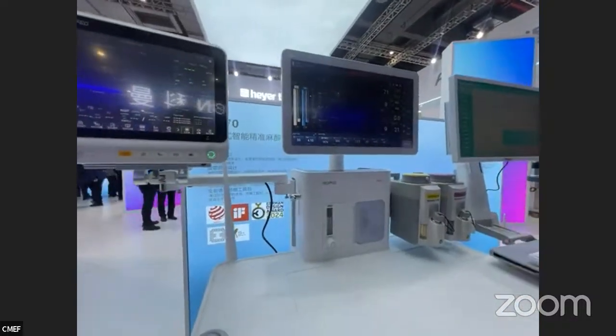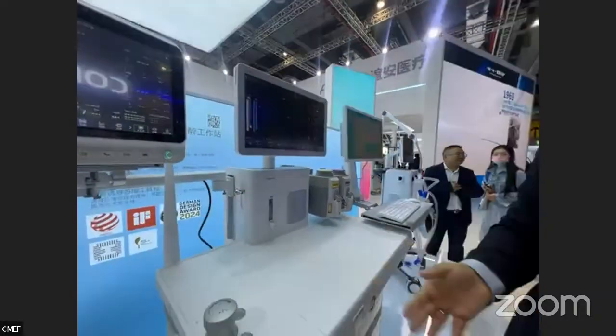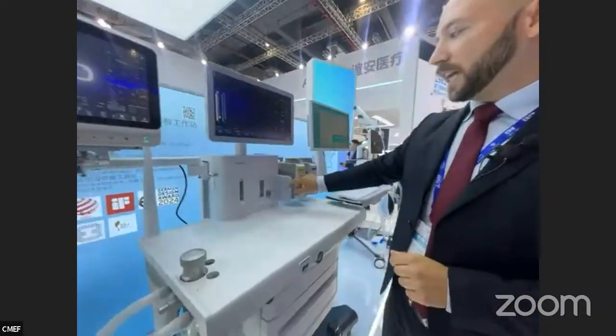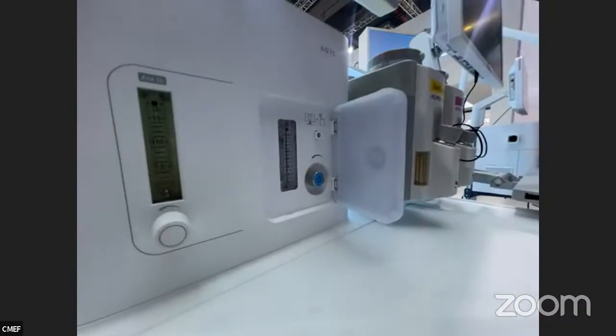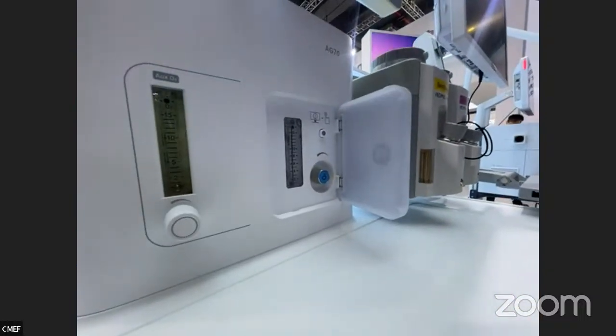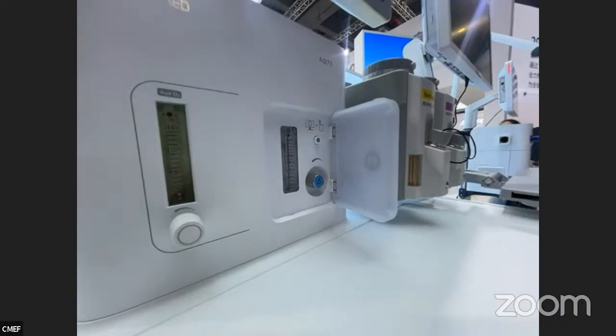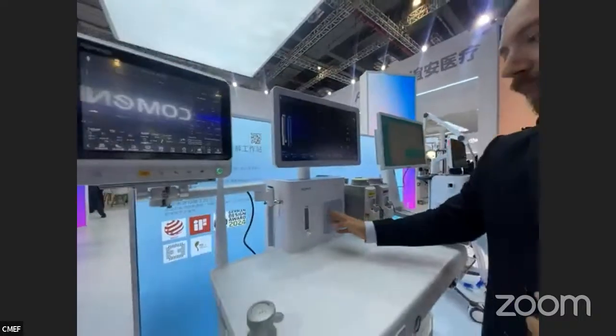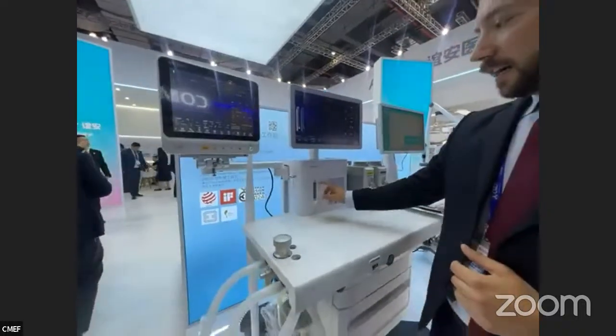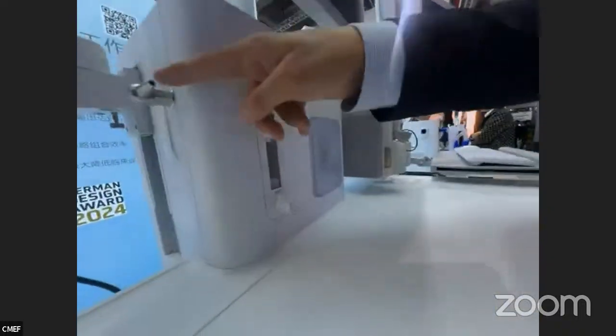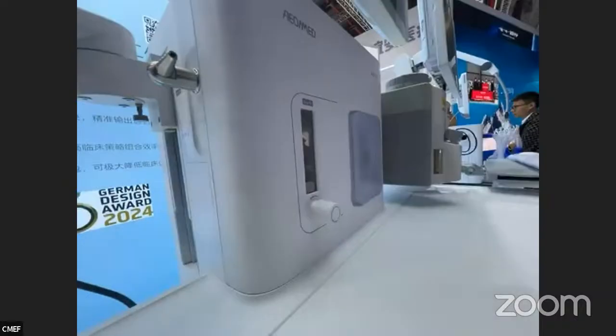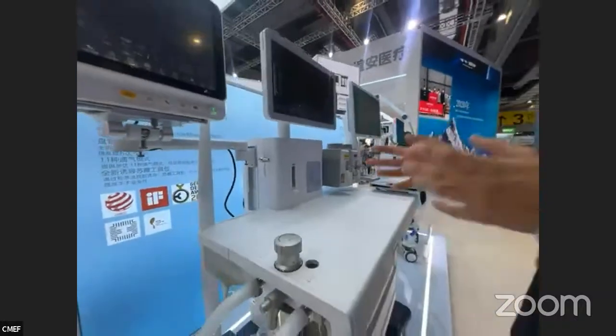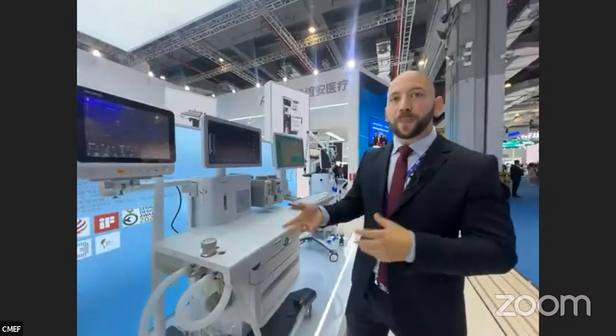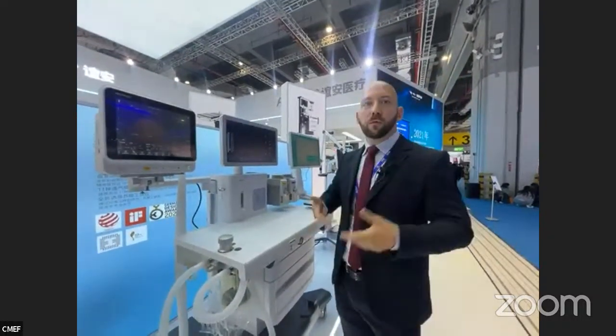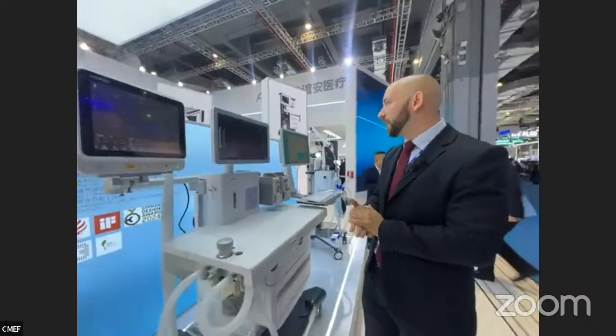and by reducing the total flow of the gas, we can actually reduce the consumption of these gases. Of course, electronic flow meters are one of the key features nowadays, but we must always have a backup plan. In order to do that, we have a system that is basically a backup in the case of unexpected failure of the electronic flow meter. In addition to that, we also provide auxiliary oxygen, where we can connect a tube to a nasal cannula, and we can provide conventional oxygen therapy to the patient before and after surgery to increase the oxygenation.